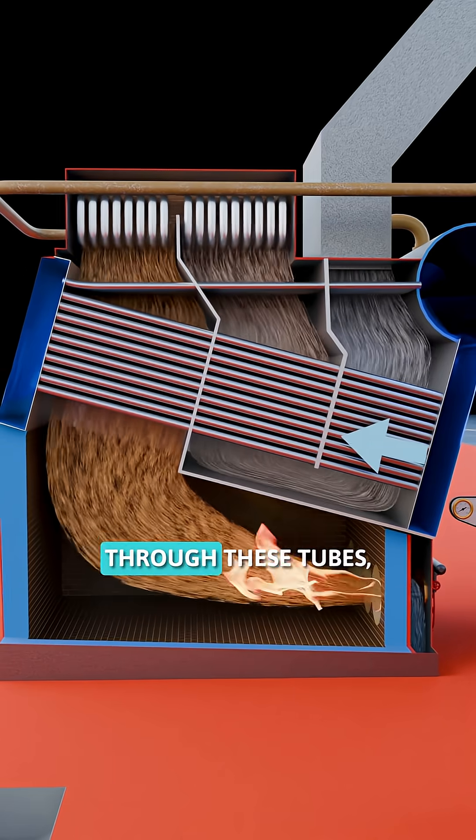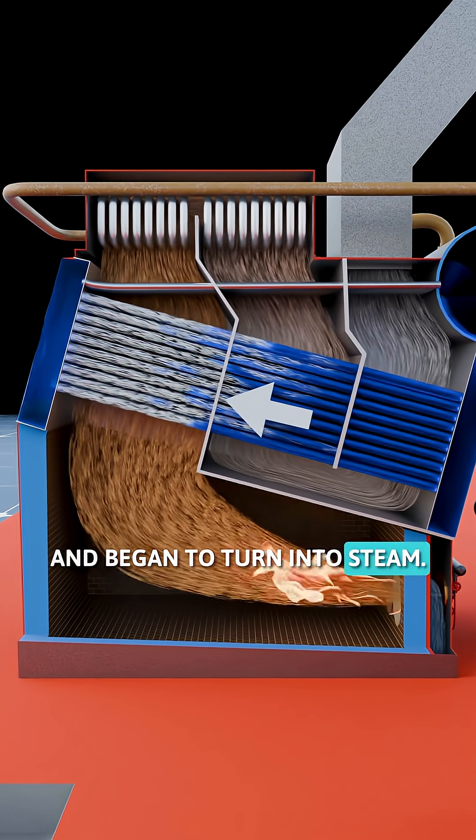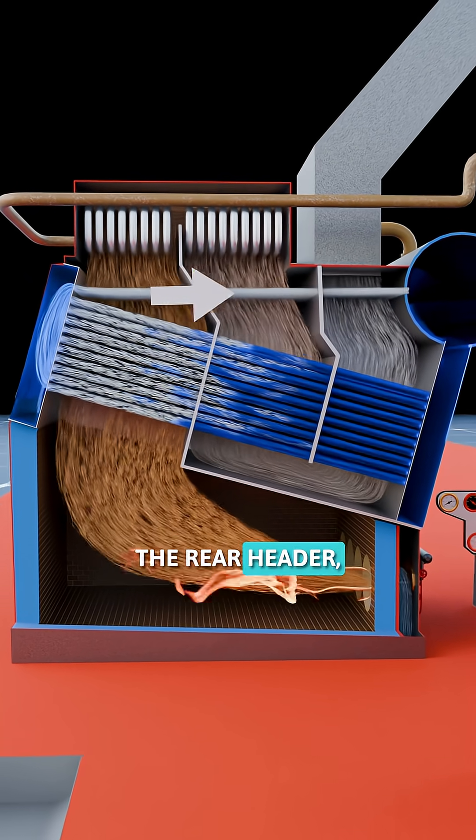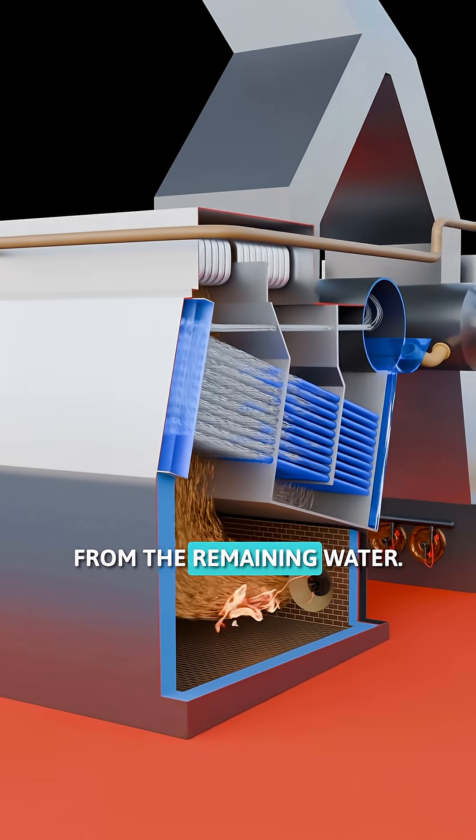As the water moved through these tubes, it absorbed heat from the combustion gases and began to turn into steam. The resulting steam-water mixture flowed into the rear header, then back into the steam drum where steam was separated from the remaining water.